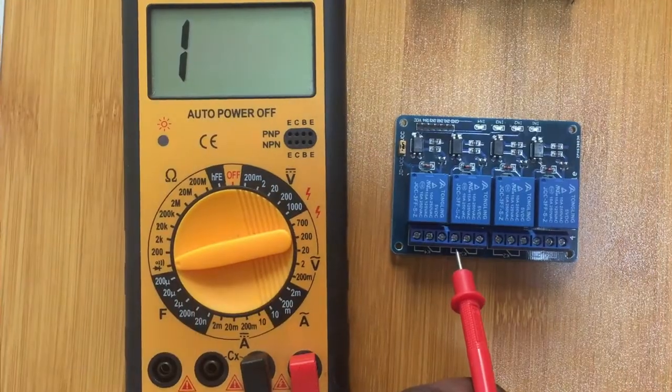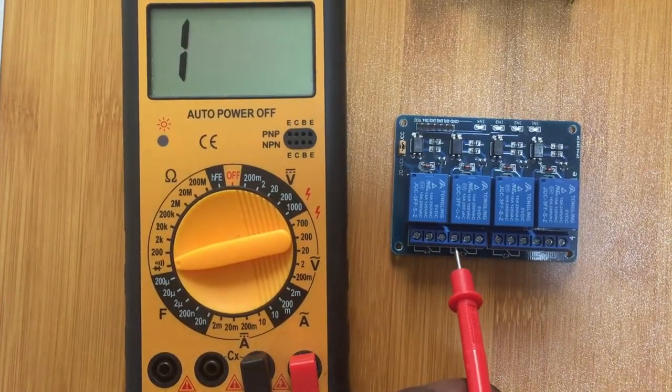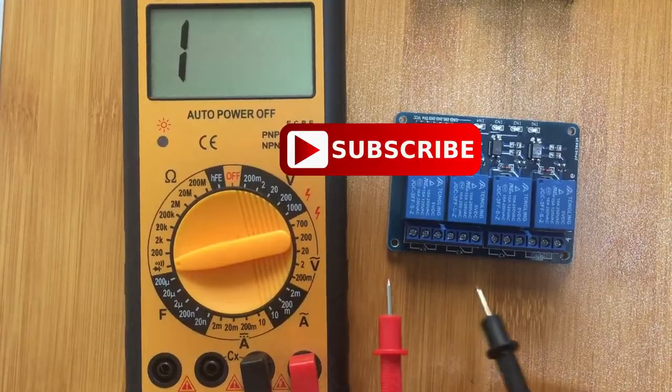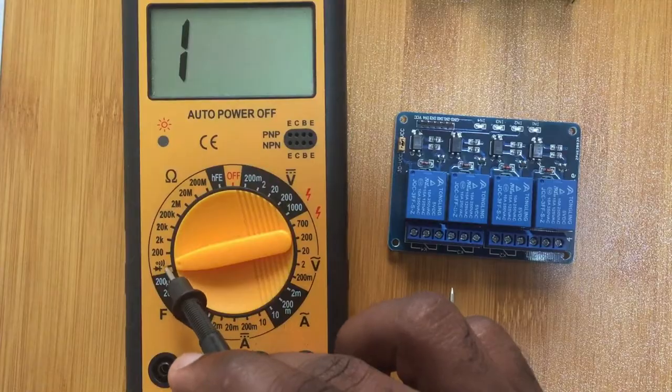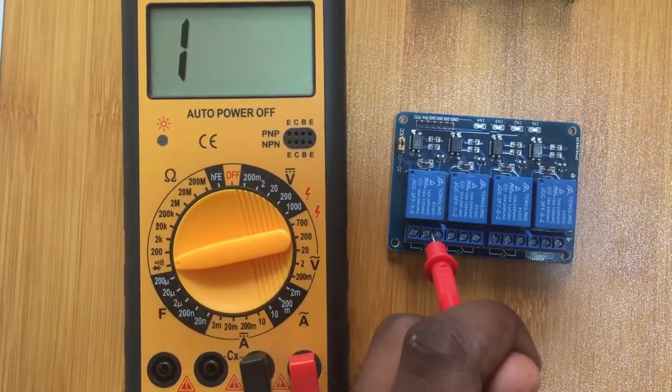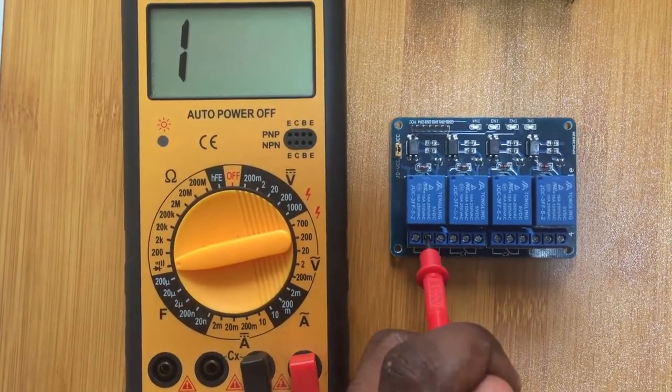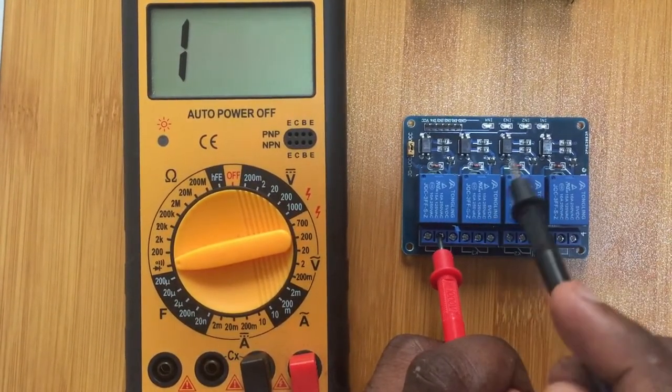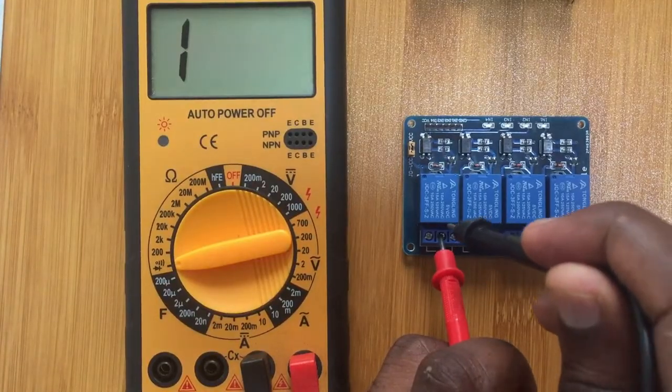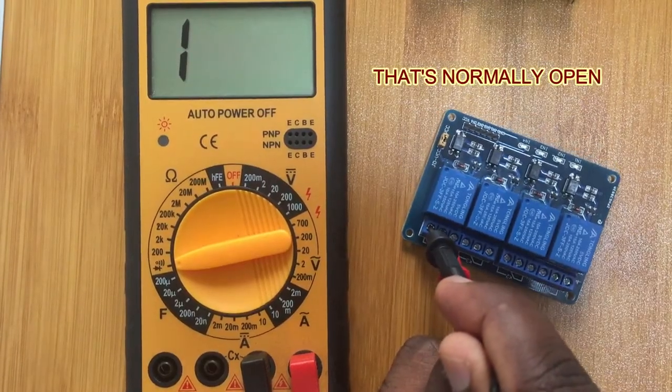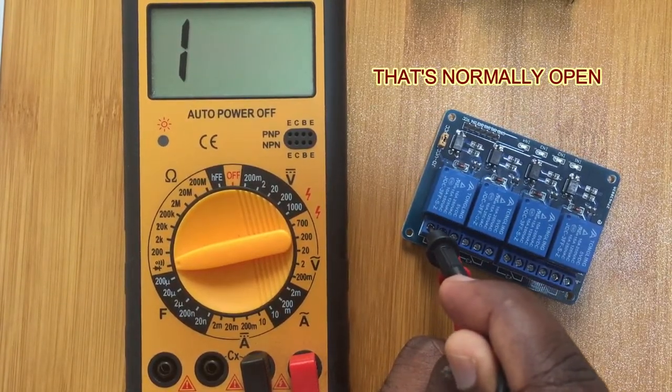We can use the multimeter to determine which of the inputs is normally open and normally closed. So if I set our multimeter here for the continuity mode, then place our positive terminal on the common terminal, then we test for which one is normally open. For example, if you put here, you observe nothing, therefore this is the normally open terminal.